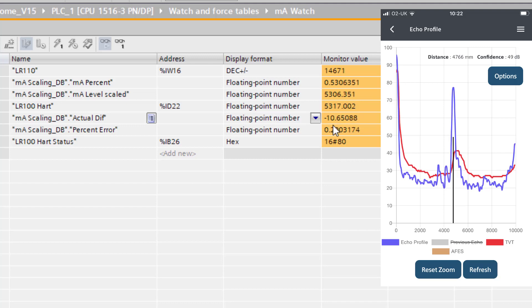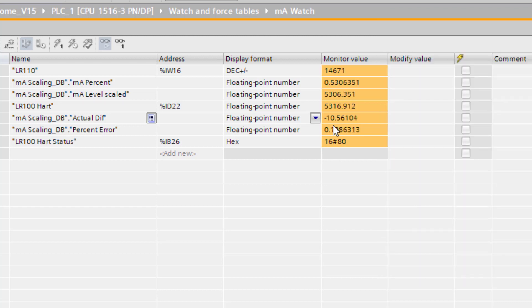I could put smoothing on the milliamps but I've still got a 10 mm error, and I'm only about four meters away as you can see from the echo profile. The argument is: some applications have people asking for a 2 mm accurate radar, a 1 mm accurate radar — and then they put it into a PLC milliamp input card and all of that accuracy is completely eroded. But if we look at the digital HART value, that is the accuracy you've asked for — the 2 mm or 1 mm accuracy. Strangely, this accuracy seems to be a fixed percentage.